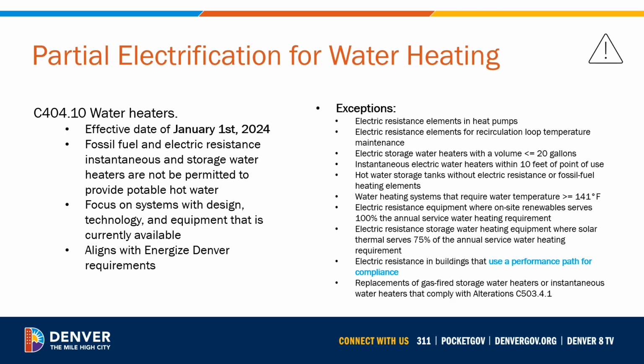Starting January 1st, 2024, fossil fuel and electric resistance instantaneous and storage water heaters are not permitted for water heating. It is important to note that this requirement does not apply to water heating systems with separate storage. This mandatory requirement is put in place to align the new construction code with the Energize Denver ordinance for existing buildings, specifically focusing on the easy to electrify systems where heat pump equipment is readily available and feasible.